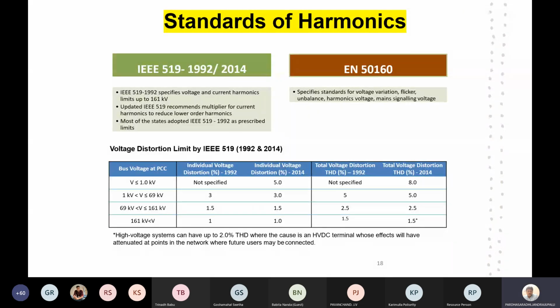What are they saying about the harmonics? IEEE as well as EN 50160, these are the two different standards. EN 50160 specifies the standards for voltage variation, flicker, unbalance, harmonic voltage and mains signaling voltage, whereas IEEE specifies the voltage and current harmonics up to 161 kV. According to IEEE 519, 1992 and 2014, bus voltage at the point of common coupling.